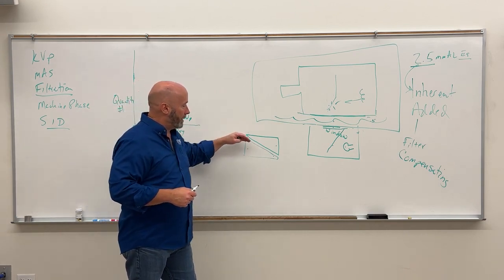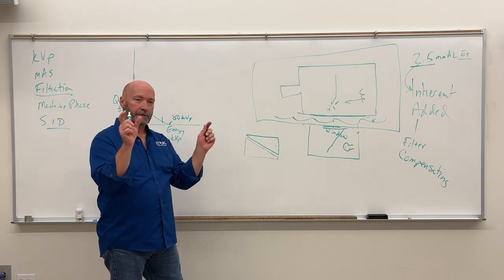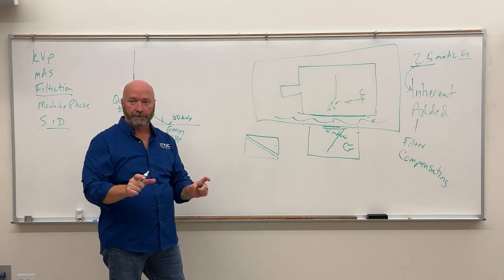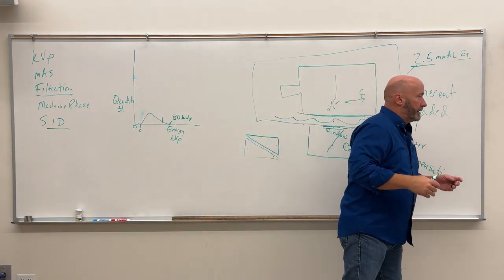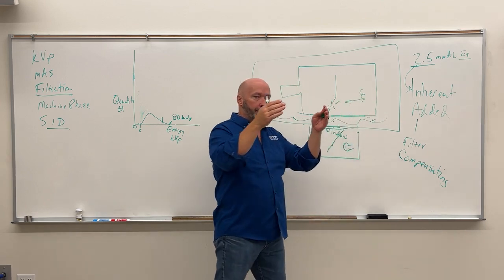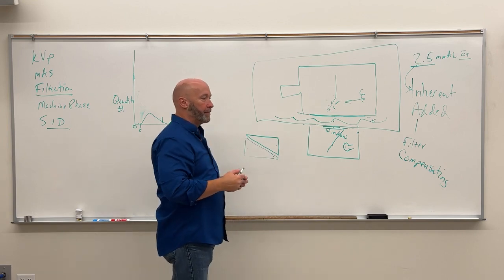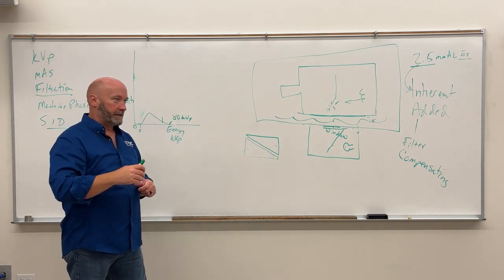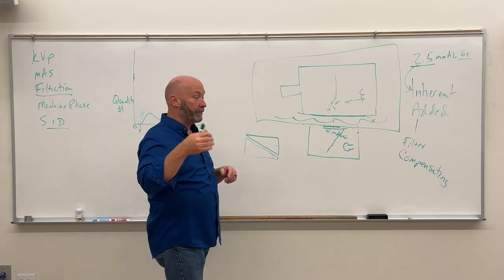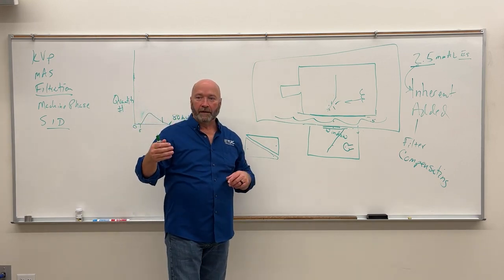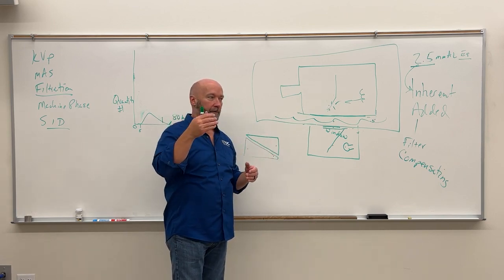Where the wedge filter was big, the trough filter is two small filters that run, if I was shooting a chest x-ray, then the trough filter would be oriented so that the filters were running up and down, okay? And the purpose for the trough filter is to provide an extra layer of beam absorption and protection on scoliosis series.